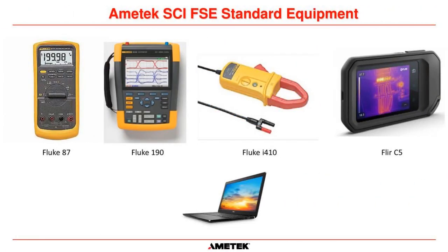Now, this is all the equipment that is standard for all of the Ametek solid-state controls FSEs out there in the field. Every one of our FSEs carries one of these pieces of equipment. So you can see we use a Fluke 87 true RMS volt multimeter. Every person carries a Fluke 190 2-channel oscilloscope. They carry a Fluke i410 minimum. They usually carry another amp clamp with them as well to measure current.